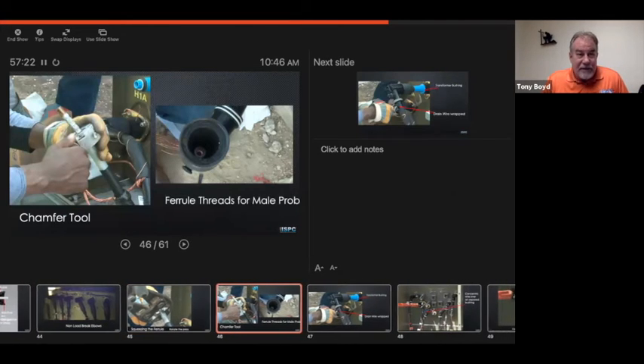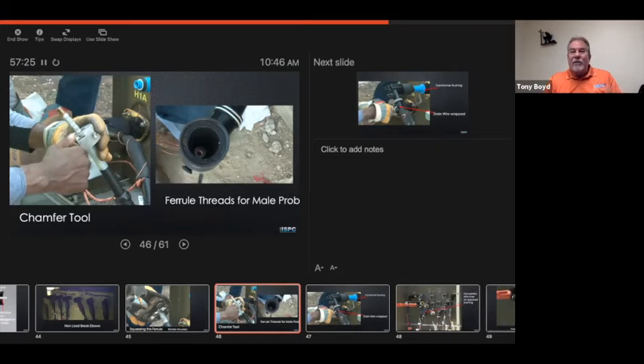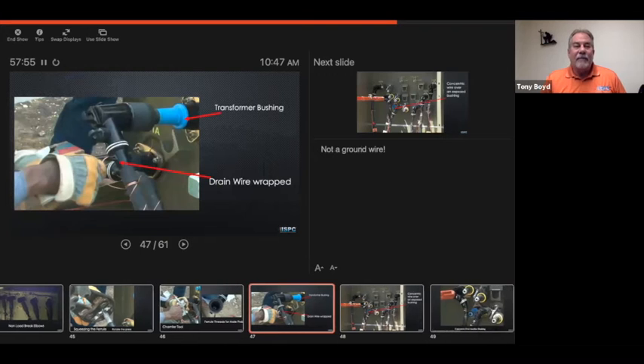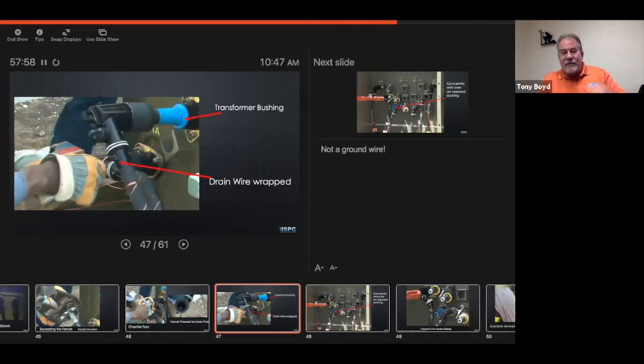This is the chamfer tool that I mentioned earlier. When you're putting on an elbow or some splices, always follow the instructions. It requires that you make a chamfer on the end of the cable. So you've just made up the cable. It's got a sharp edge on it. Sliding the elbow on or the splice body on could damage some of the inside of the elbow and leave a scarring mark that would leave a track for later on when we energize it. So the chamfer tool smooths that off, so when you're sliding the elbow on, it makes a smoother process.